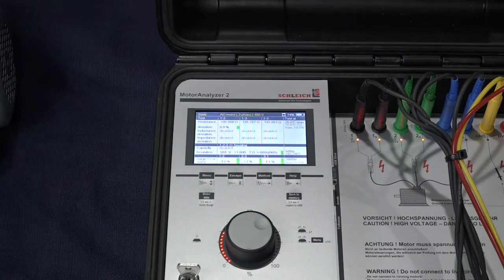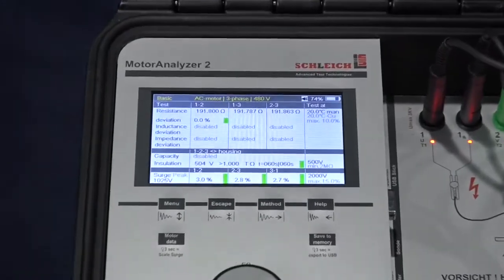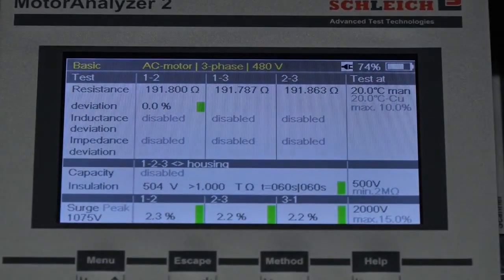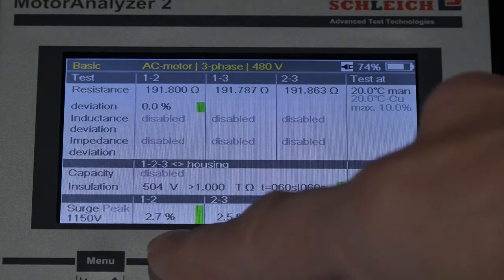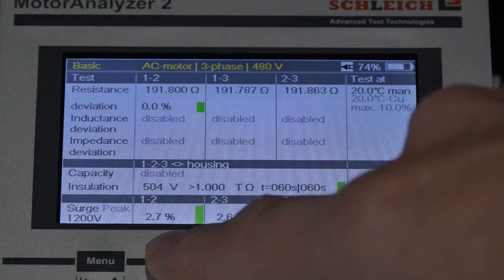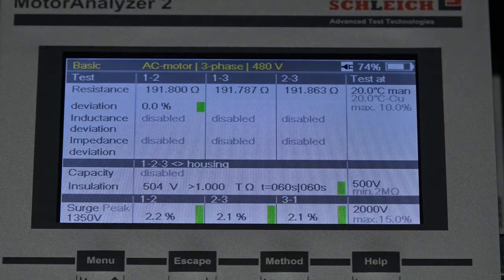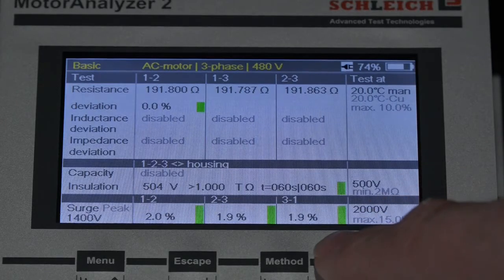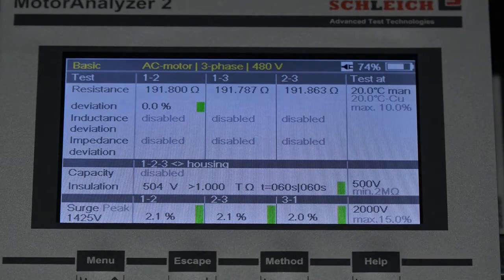Again, we're going to take 3 surge tests at a given voltage on all 3 leads, and then we'll increase the voltage. Now this is different than the way most surge testers have worked in the past, but the guys found that this is really a very effective way to test an assembled motor. Now the EAR numbers that you see down here are pulse-to-pulse EAR numbers. So we'll compare, say, the test at 1200 volts to the test at 1225 volts for just lead 1 to 2. If there is an arcing fault, these numbers are going to jump up very high, and it'll be very obvious.